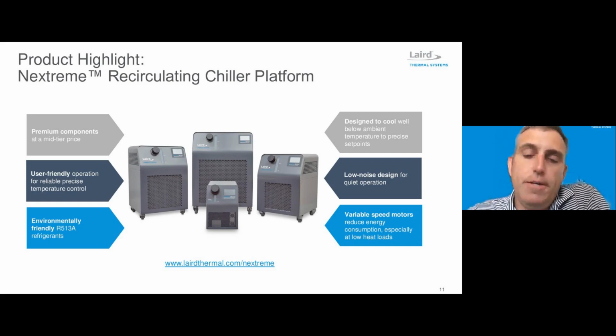The system also has very low noise. There's a couple of reasons for this. One of them is the actual fan that's been used in the system. I had mentioned earlier that some of the technological advances in heat exchangers have come a long way. A couple of decades ago, maybe even just 10 years ago, the majority of the condensing units used in these systems were what we call a tube fin variety. So very low performance, maybe 70% efficient. The technology that's commonly used today and what's been employed here is a microchannel heat exchanger. So very efficient heat exchange takes place here, probably upwards of 90%.